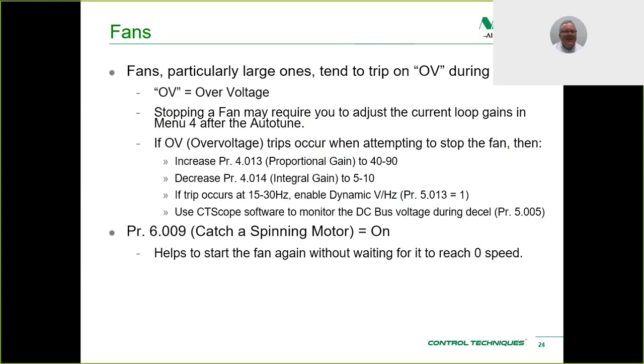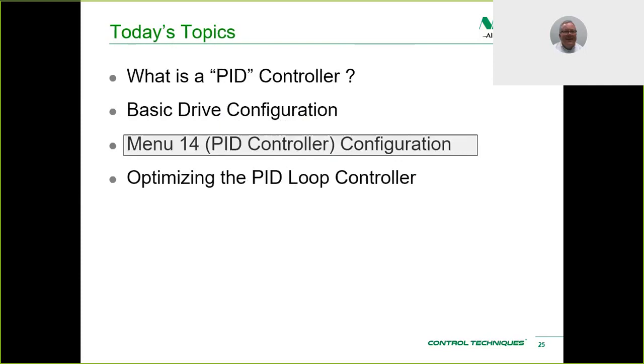What catch a spinning motor does is it tries to estimate what the current frequency is as it's sitting there spinning so that you can start it faster. So it'll try to pick up where it is, in other words, and go from there. So that's a handy parameter for restarting the fan after it's been stopped. So those are the basic settings for our drive.